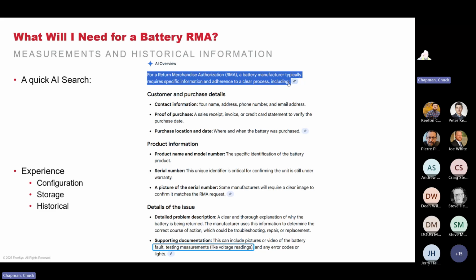So the other thing you need is historical information to fill out a battery RMA. Most manufacturers of batteries will require you to have historical data. Again, a reason to have a connected infrastructure with the batteries monitored. Bringing that battery information back allows the people handling the RMA to effectively calculate what the problems were.